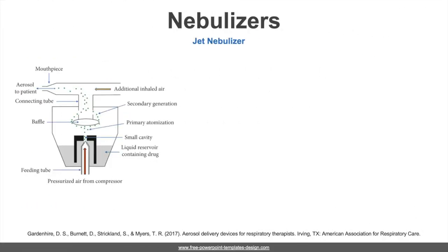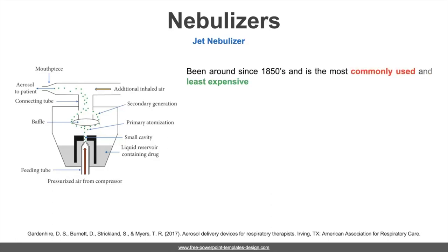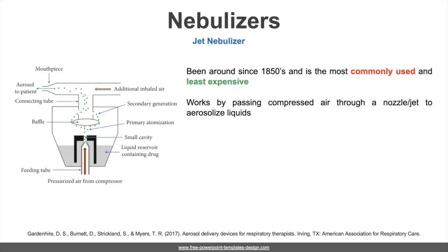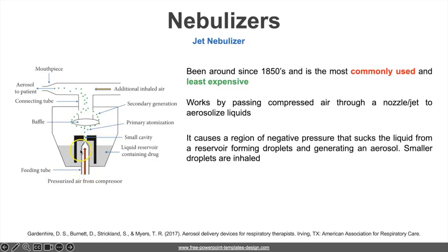Jet nebulizers have been in use since the 1850s and remain the most commonly utilized and cost-effective option. They operate by directing high-pressure air or compressed gas through a nozzle or jet to aerosolize liquids. As the compressed gas passes through the jet, it creates a zone of reduced pressure that draws liquid from a reservoir, causing it to fragment into droplets, generating an aerosol of both large and small droplets. The small droplets are inhaled by the patient, while larger droplets are intercepted by a baffle that redirects them back into the reservoir for recirculation.